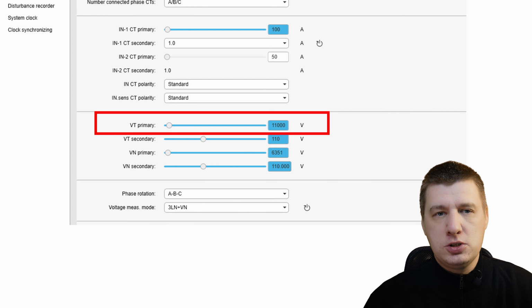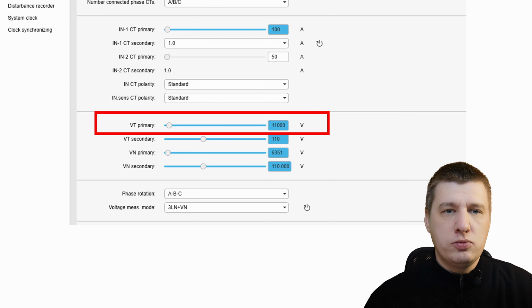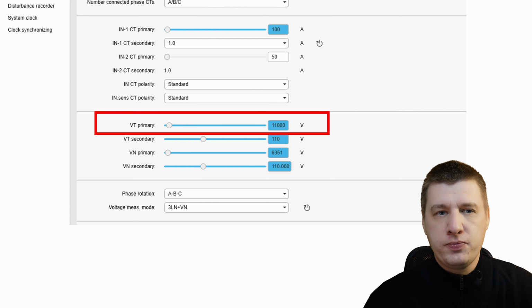Let's use an example. Suppose your network runs at 11 kilovolts. Your physical voltage transformers might have a ratio of 11,000 volts to 110 volts. In this scenario, you would set your VT primary to 11,000 volts. This acts as a mathematical bridge. If the relay detects 110 volts at its back terminals, the secondary, it uses that 11,000 volts setting to display the correct primary values. The P5 is incredibly versatile.